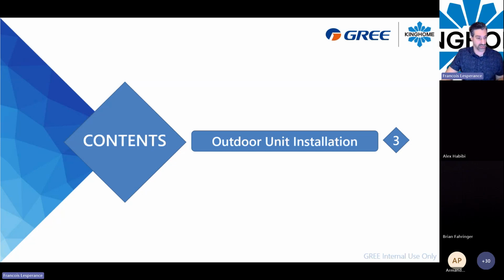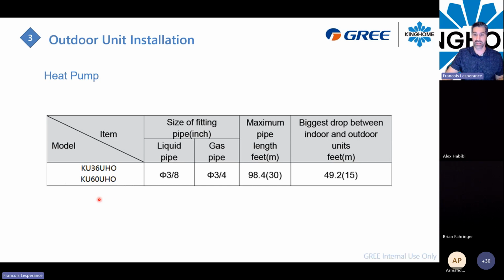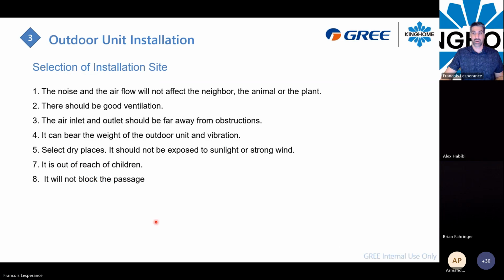We're just moving forward with the outdoor installation. I already talked about there being 2 kinds of outdoor unit, but the 3-ton unit can be configurable as a 2-ton, and the 5-ton can be configurable as a 4-ton. The pipe size for any kind of unit will be 3/8 and 3/4. You can have a maximal pipe length of 98 feet, and the drop between those 2 units can be 49 feet.